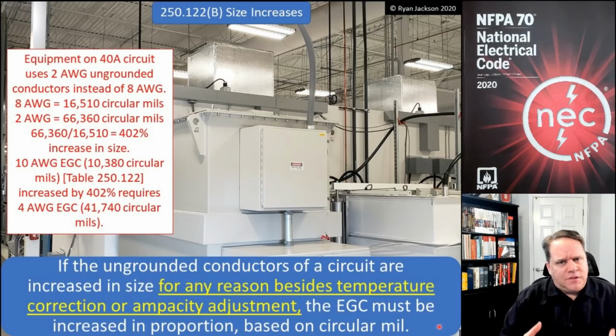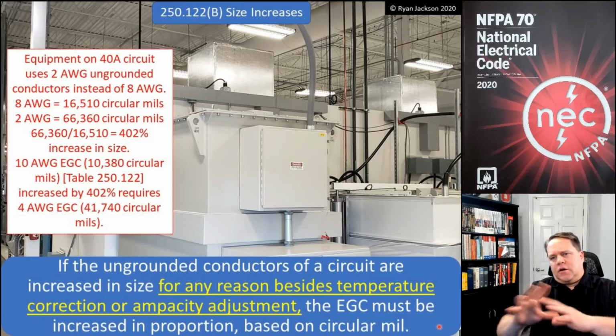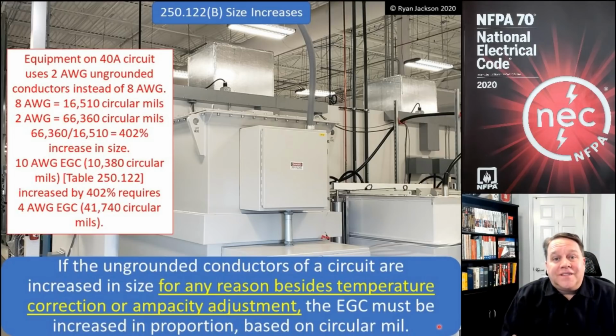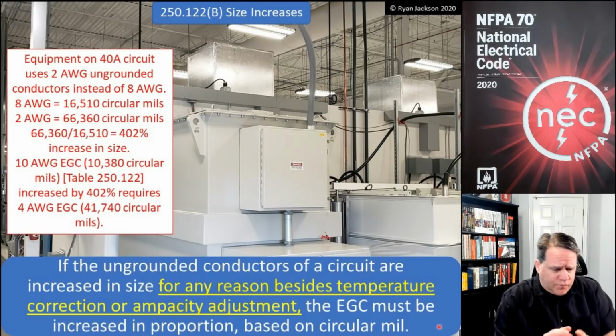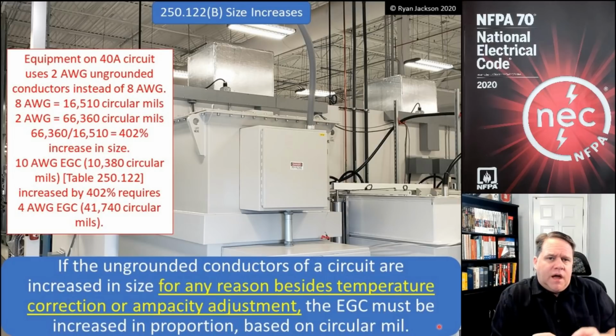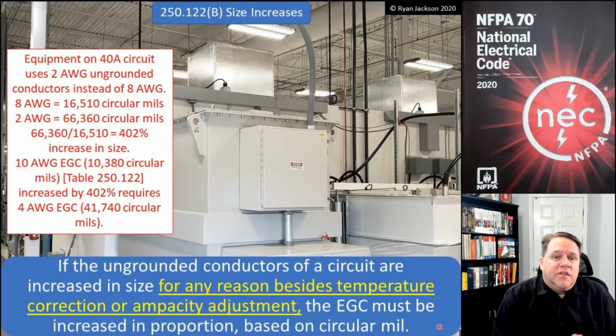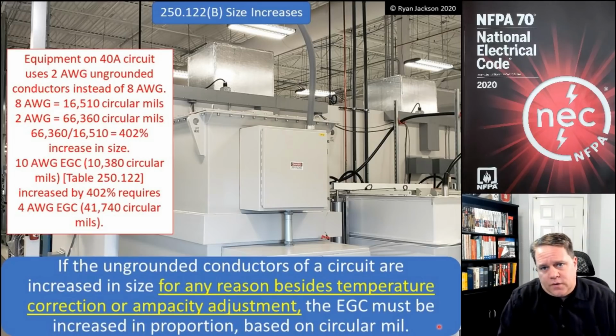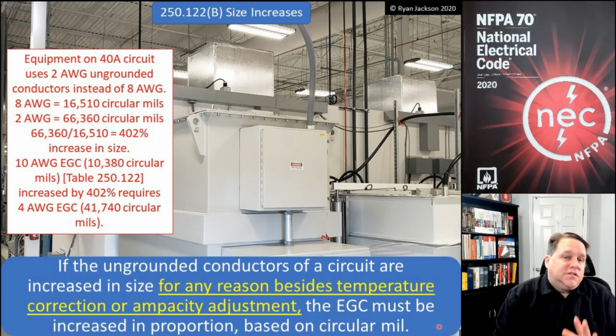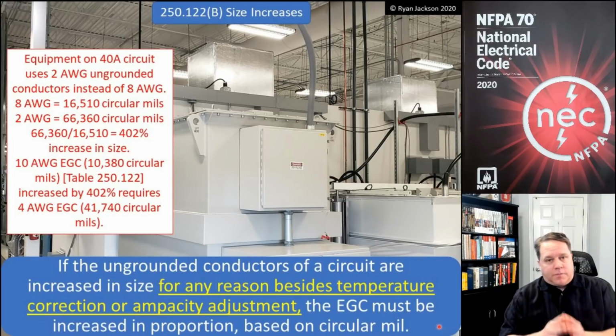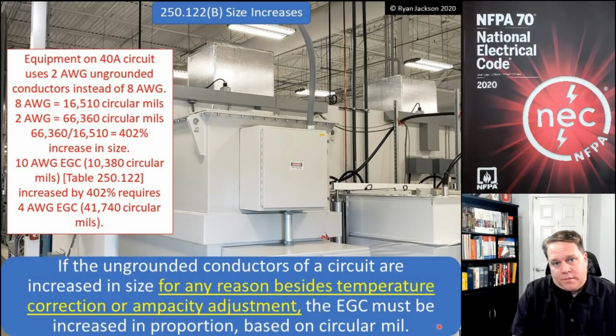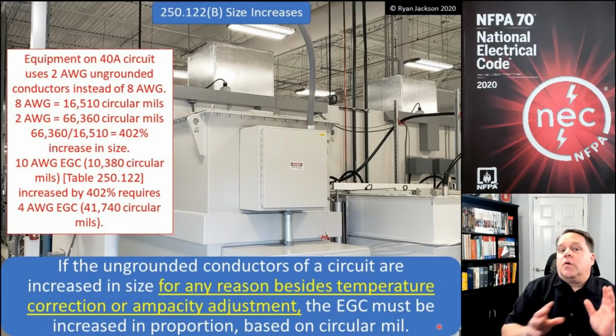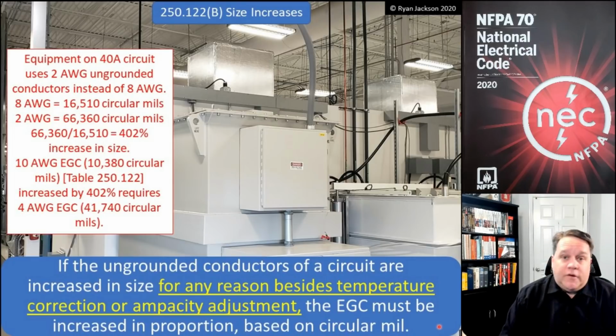And you can see all of these mental gymnastics for something that really doesn't matter, right? If we're not increasing it for voltage drop and we're not making a gross misapplication, this section probably isn't that big of a deal. So how do we write this rule? And by the way, for the 2020 code, this is such a problematic section. And like I said earlier, I think it's impossible to make this section perfect. So what they did for the 2020 code is there were so many proposals to change 250.122(B), and the proposals all solved different parts of the problem. None of them solved all of the problem. So Code-Making Panel 5, what they did is they said, look, obviously we have a problem. We need to fix 250.122(B). How do we do it?